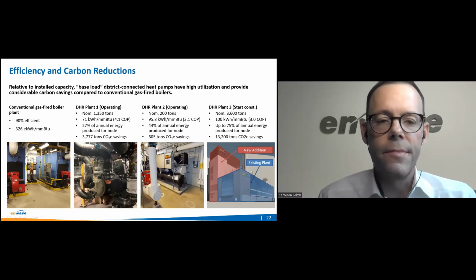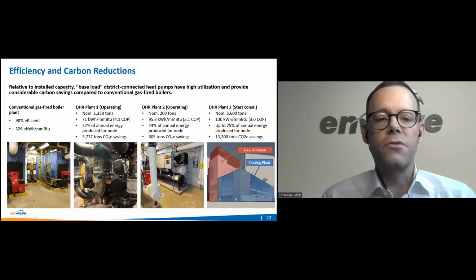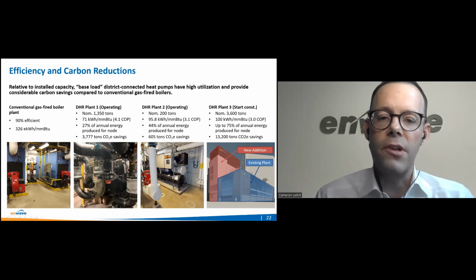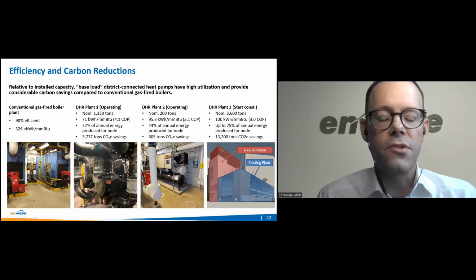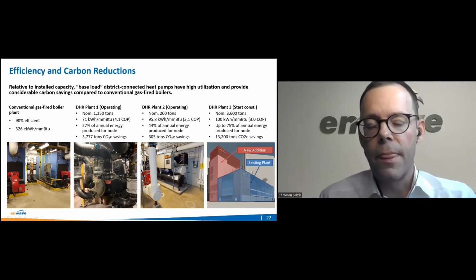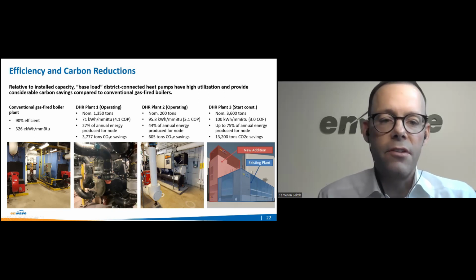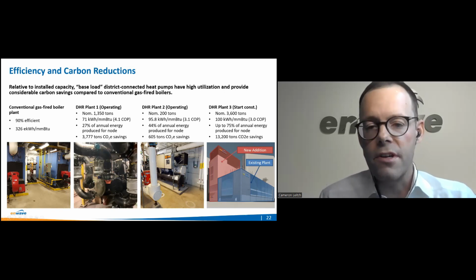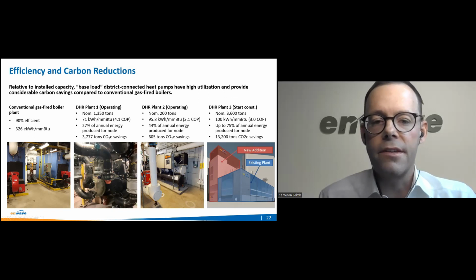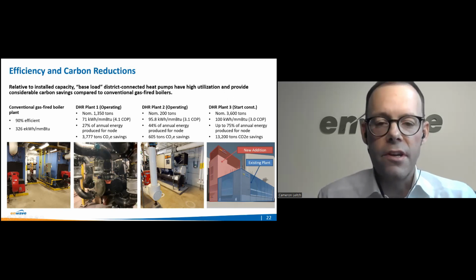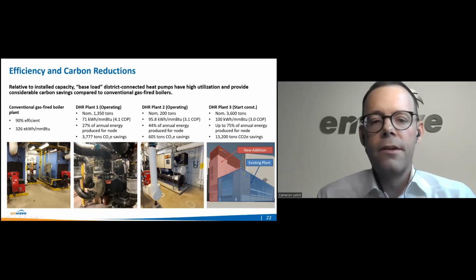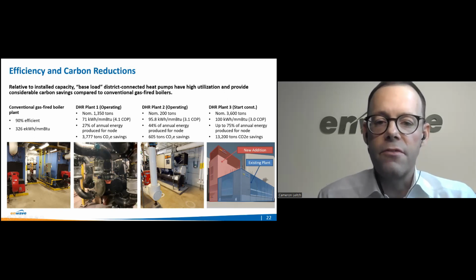pump capacities. For example, DHR Plant 1 has heat recovery chillers equal to approximately 10% of the installed plant capacity, but produces almost 30% of the annual heating energy. DHR Plant 3 will have heat recovery chillers totaling less than 30% of the total installed capacity of the plant, but produce up to 75% of the annual heating energy. These high utilization factors are reflected in the carbon savings noted.